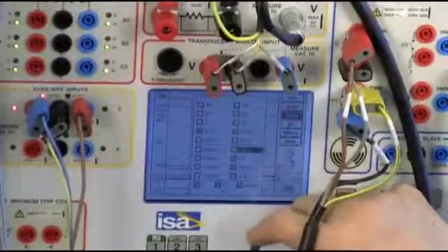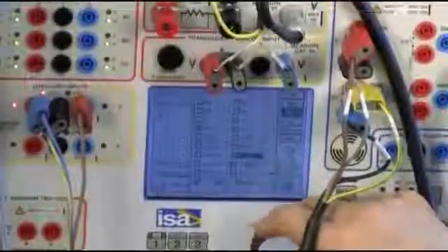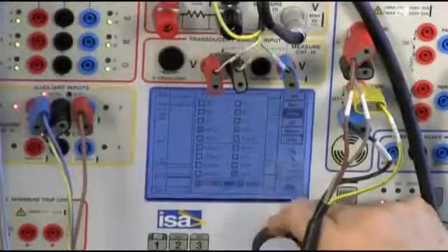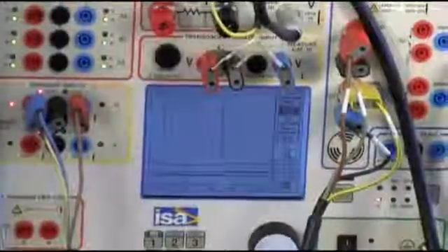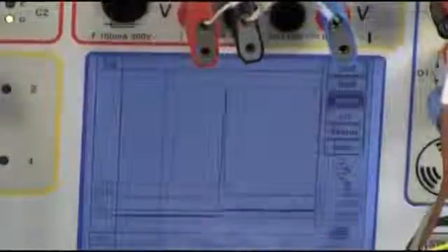Okay, so I come again to view. I unselect the voltage, the 500 volts that is the transducer. I unselect the current, and I select the micro-ohmmeter measurement, so that we can study it immediately. And here we are. You see that there is an open situation here. Then there is a transient, and this transient is due to the inductance of the connecting cable, this cannot be eliminated, but then you have a value here of resistance that is no more open value.